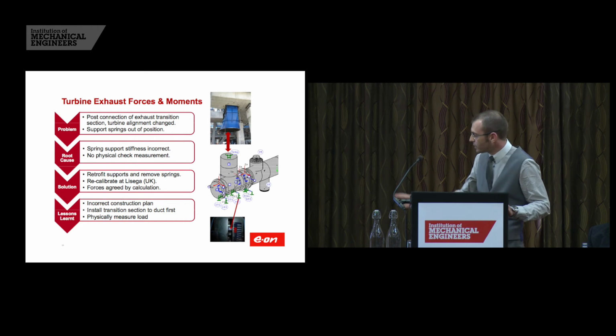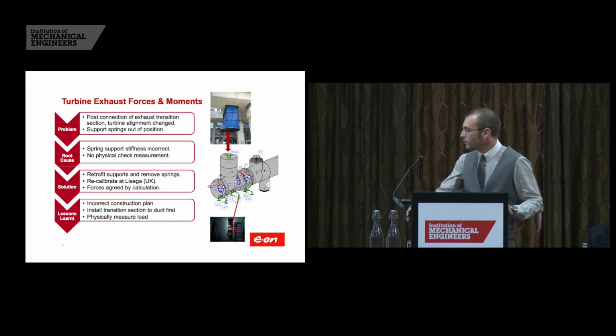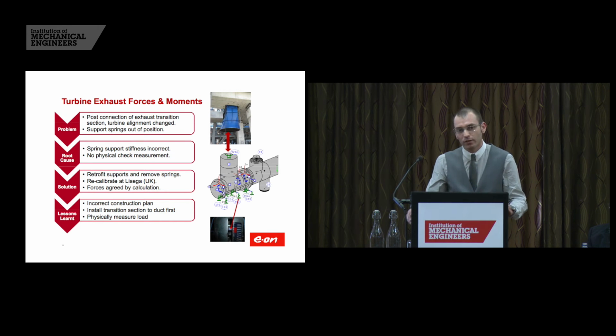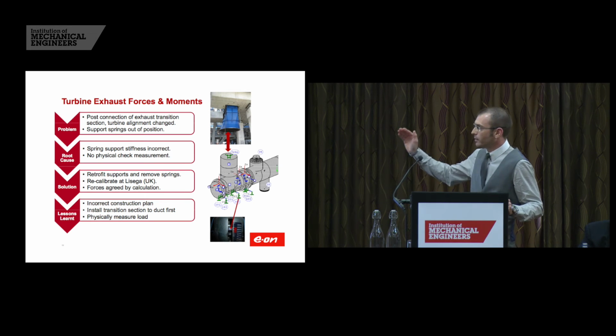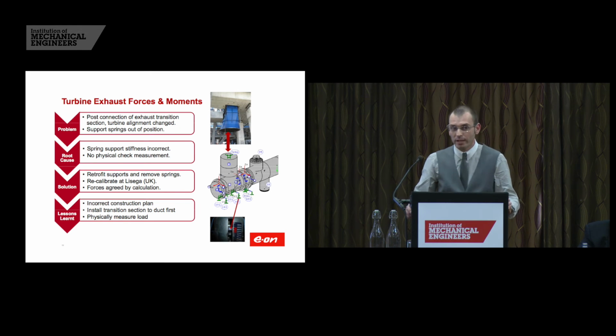Focus was drawn to the spring pots below the steam turbine duct, and it was found that the supports were sitting out of position and exerting an upward force on the steam turbine. The decision was made to check the calculations on both the ACC and turbine manufacturer. The turbine manufacturer at the exhaust had force and moment limits, as with any steam turbine. However, these limits were at the rectangular duct. The contractual termination point for the contract was at the circular duct. Therefore, the mass of the exhaust duct itself was not taken into consideration in the calculation.